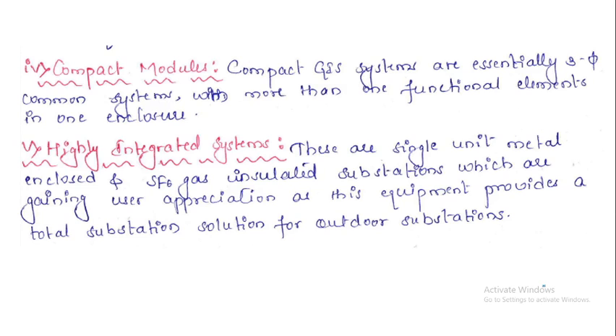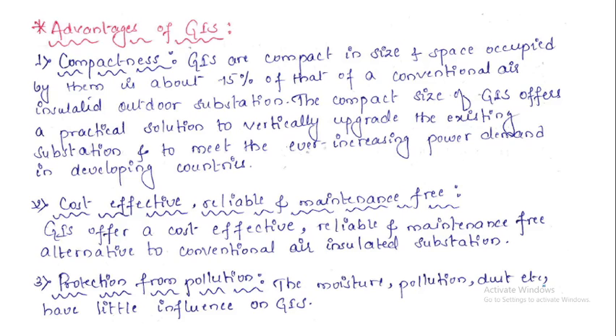These compact GIS systems are essentially three-phase common systems with more than one functional element in one enclosure. Then we have the highly integrated systems. These are single unit metal enclosed and SF6 gas insulated substations, which are gaining user appreciation as this equipment provides a total substation solution for outdoor substations. Finally, moving on to the advantages and disadvantages of GIS, very important.